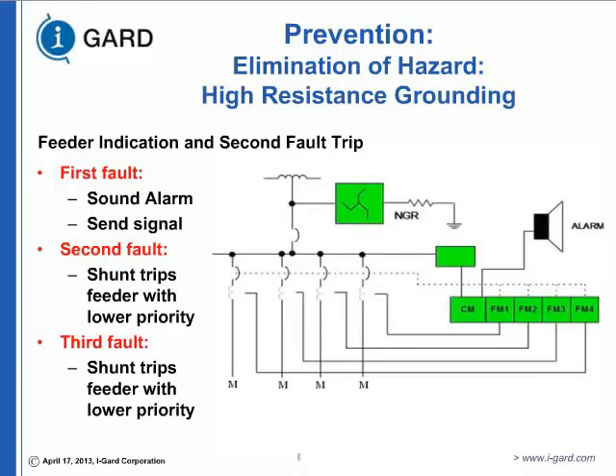High resistance grounding depends on isolation of the first fault, because the first fault is going to be whatever your resistance limits. What if you have a second fault? The second fault will go phase to phase. So if the second fault happens before you can isolate the first fault, you will have a phase-to-phase fault with very high energy.